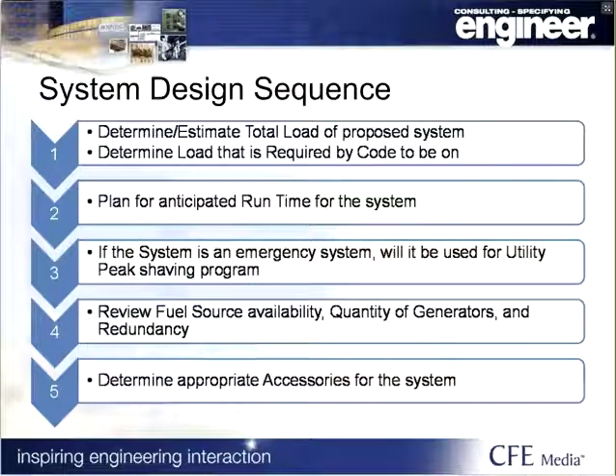It'll help you determine whether or not you're going to be going with a single generator or multiple generators. It's also important to determine what the load is by the different systems that Rob was talking about, which is the legally required, the emergency, and also the alternate non-required loads.